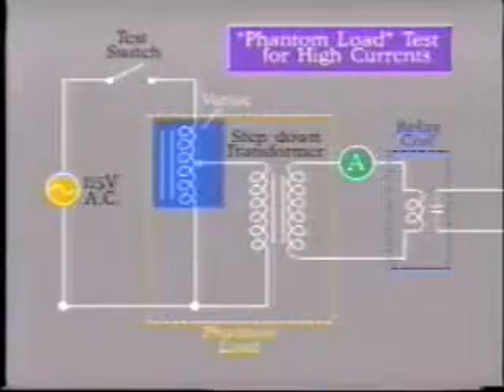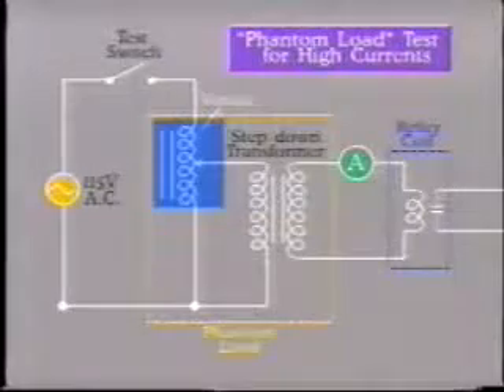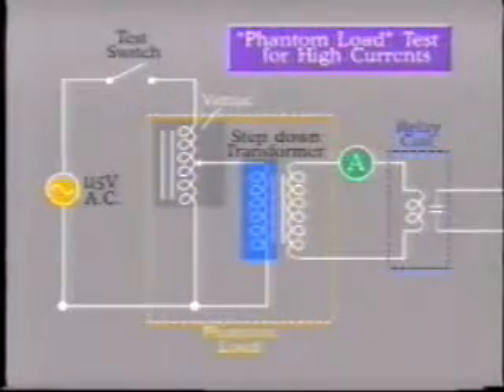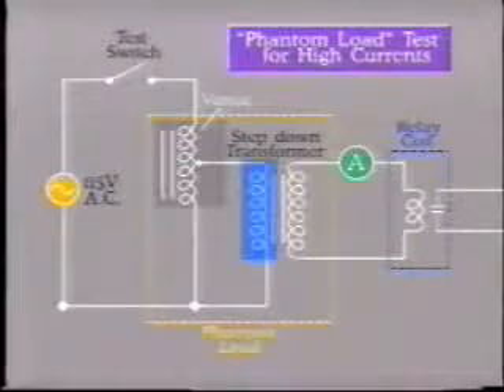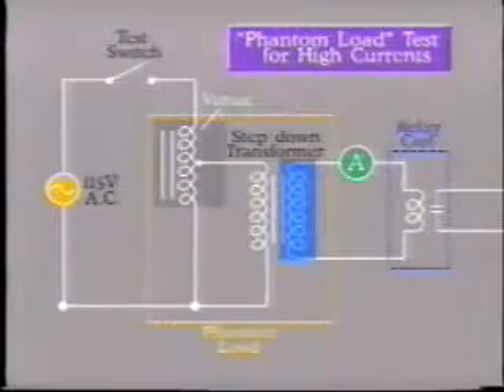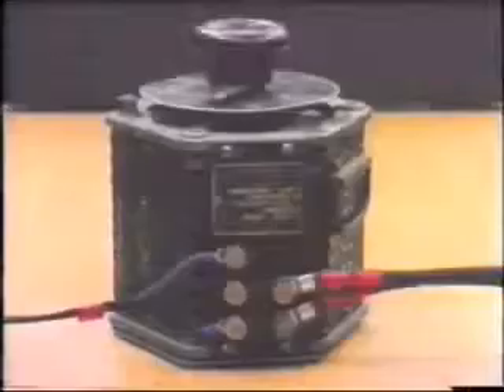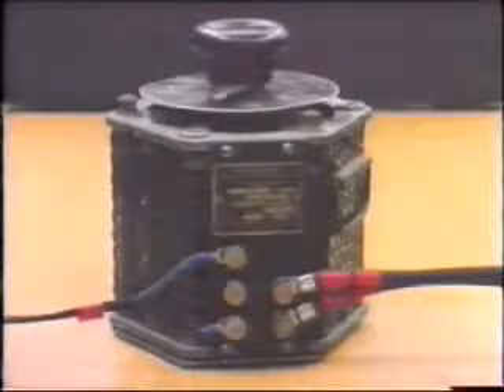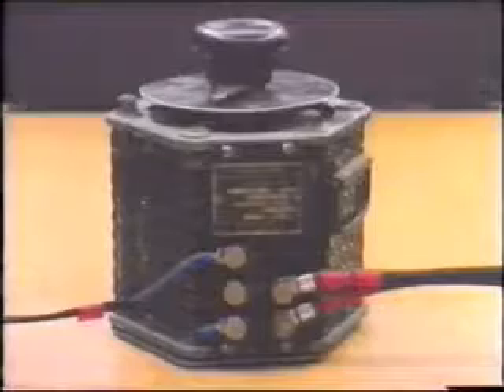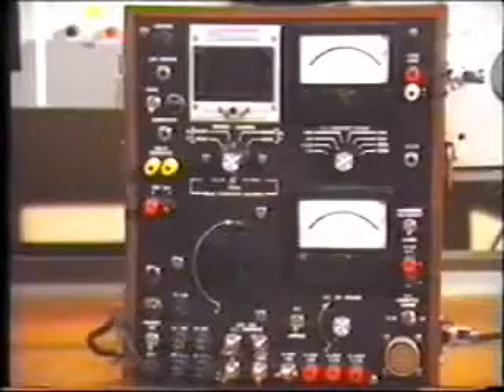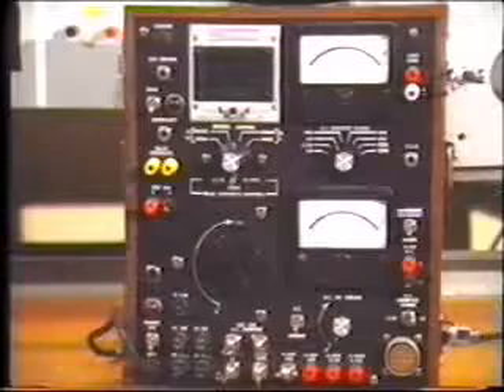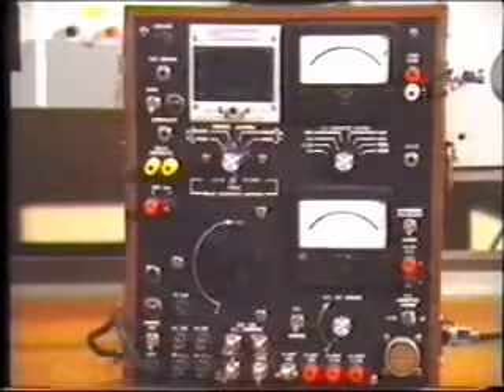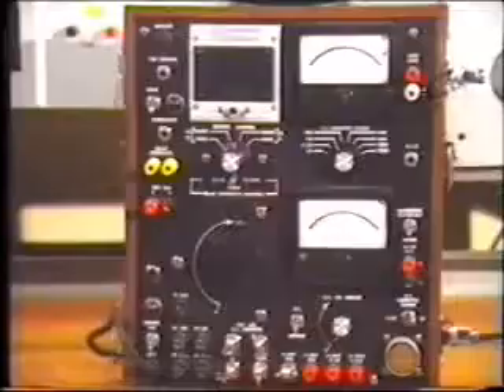This is accomplished by using a variable inductance instead of resistance, sometimes called phantom load. A variable autotransformer known as a variac provides an adjustable input to a step-down test transformer. This in turn supplies low voltage and high current to the relay. When using this arrangement, always make sure that AC input to the variac is connected with the correct polarity. Test set manufacturers offer this type of setup in a single unit, including a contact sense light and a timer.